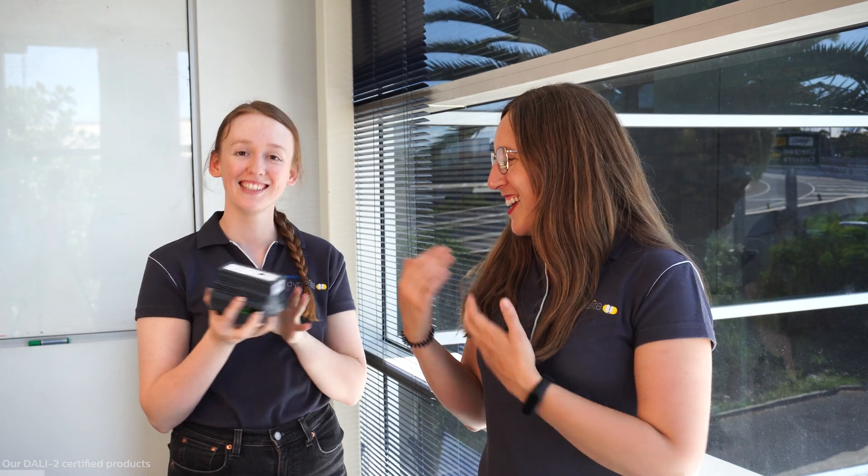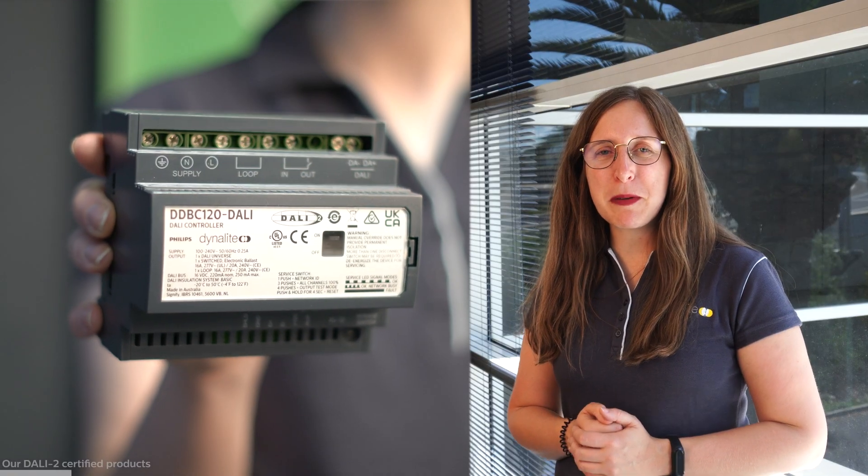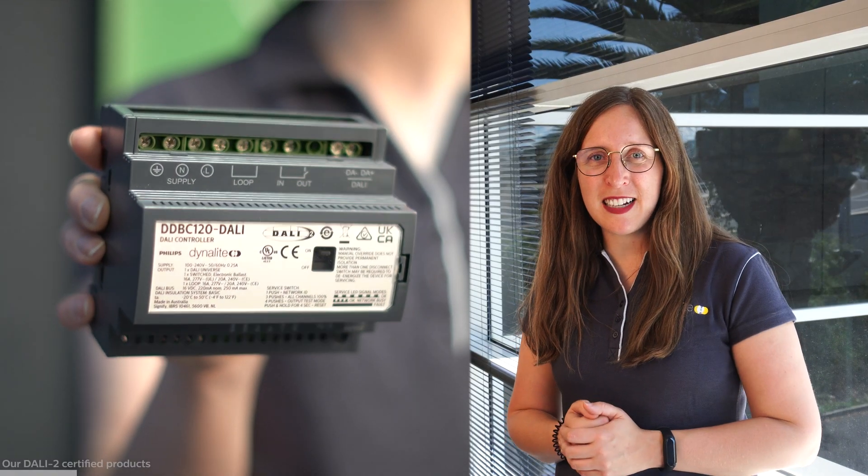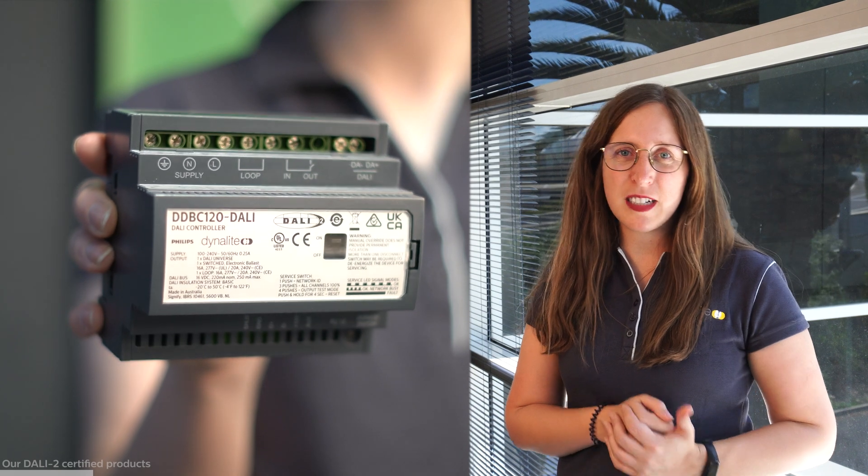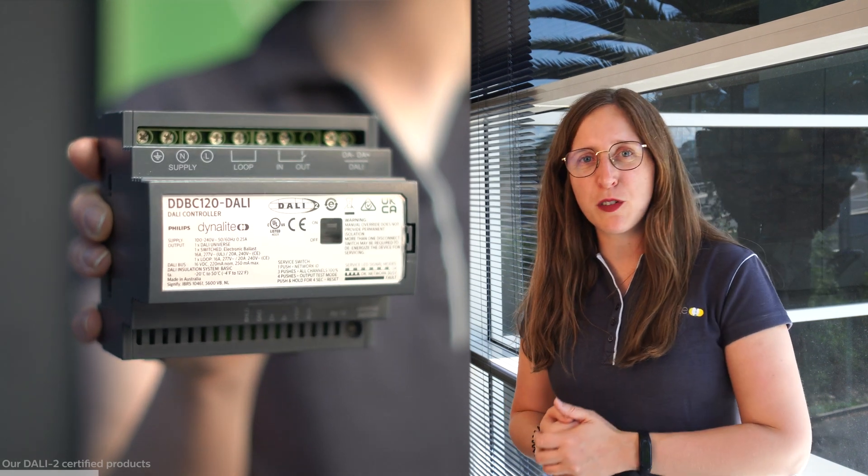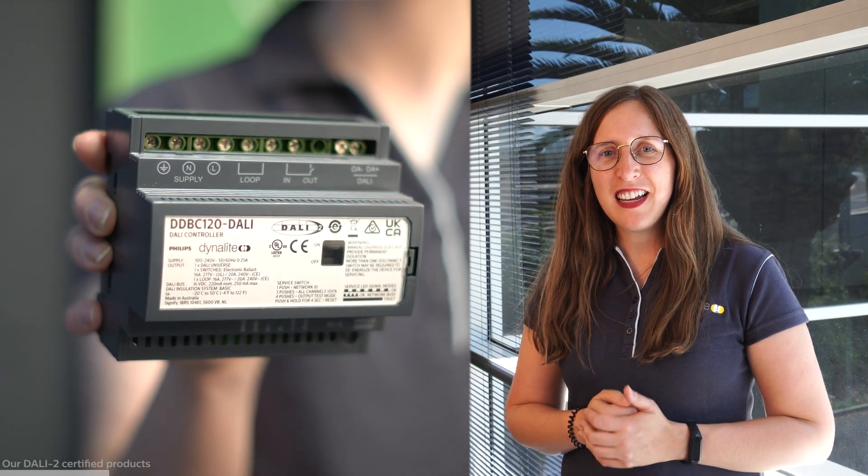So our Dynalite portfolio has two DALI-2 certified controllers. Let's first have a look at the DDBC120-DALI. Here we have a one DALI universe controller, including the power supply. Thanks to the direct mapping between DALI and Dynet we are also enabled to use 64 scenes and 64 groups compared to the 16 limitations that DALI standard has.